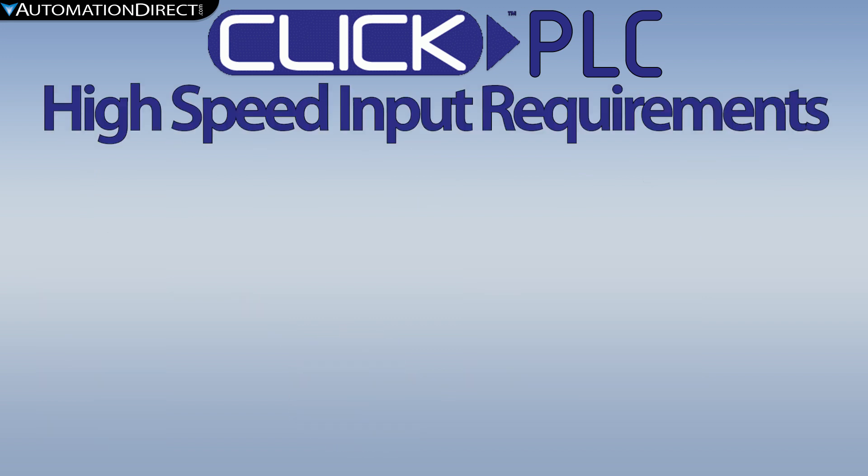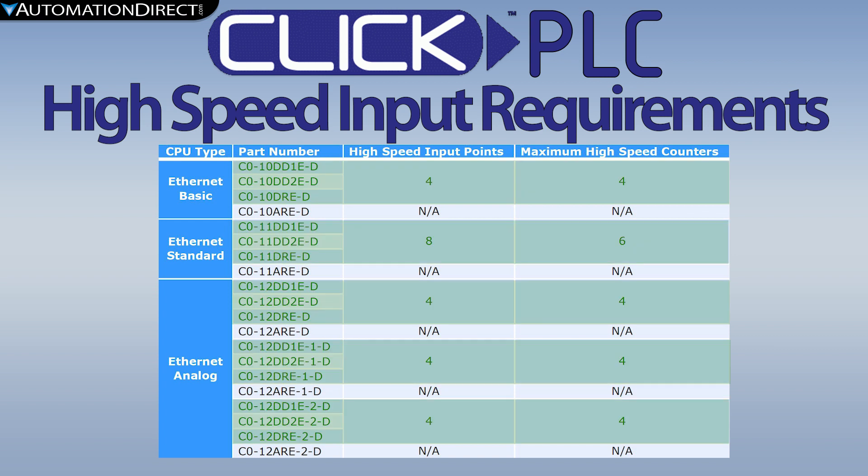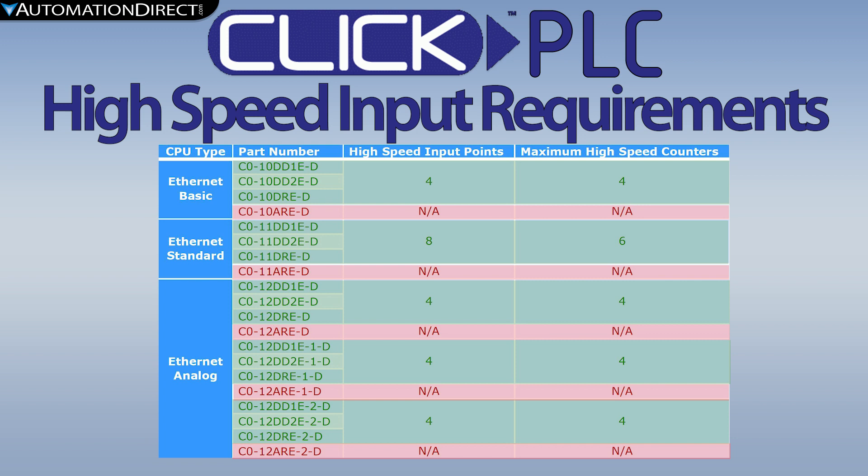To use high-speed inputs on CLICK, you must have a CLICK CPU that supports Ethernet and has DC inputs. High-speed counting is not supported on units that have AC inputs.